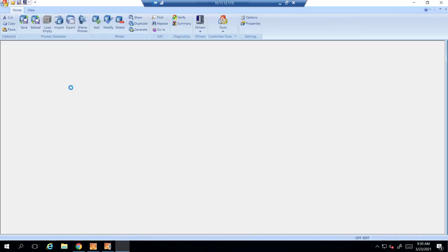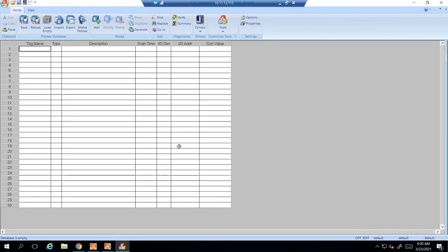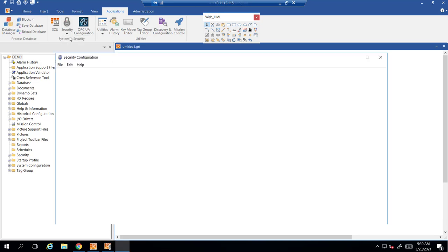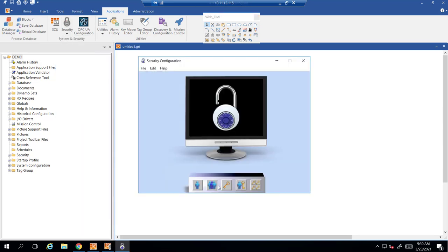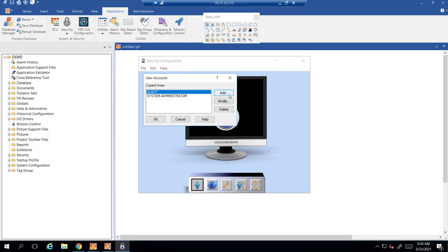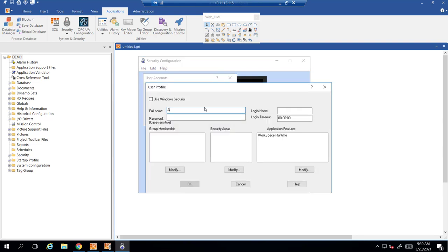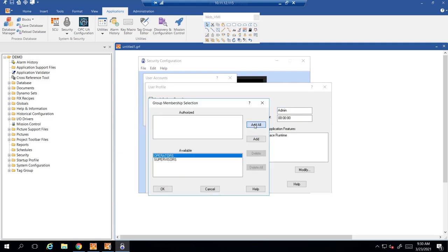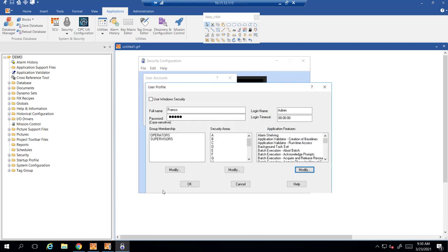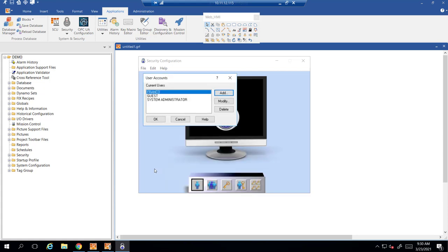From here you can go into Database Manager. Because it's an empty project, we don't really have any tags to show you, but just as an example. For basic security configuration, I like to create a master key account. Go to the small person icon, hit Add, put in your name — Franco in this case. Use an easy password to remember. If it doesn't take Admin, go ahead and just change it. Make sure you add all the selections for everything. This will create an account so you can log in no matter what — some people like to call it a master key.